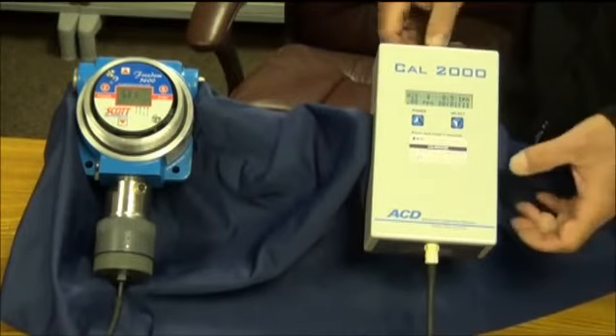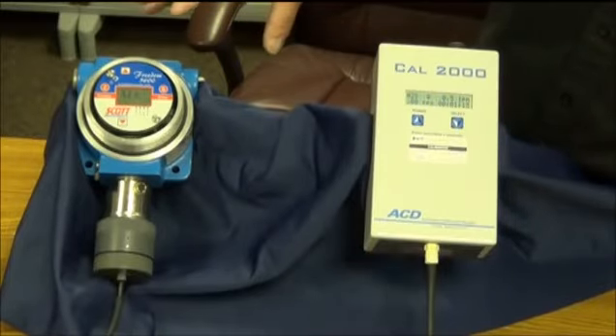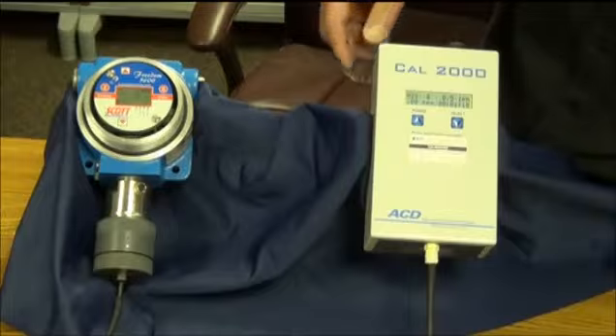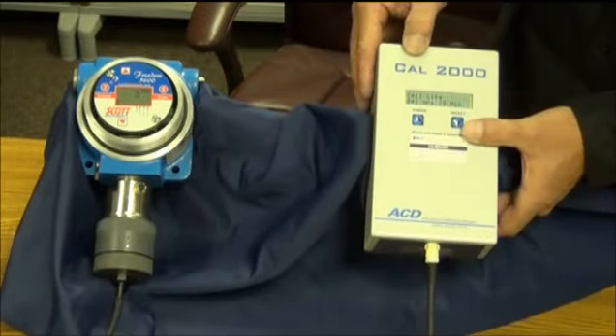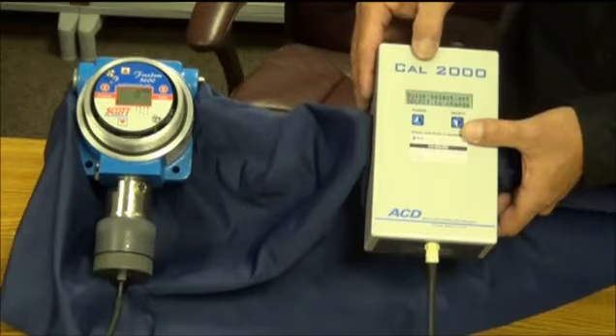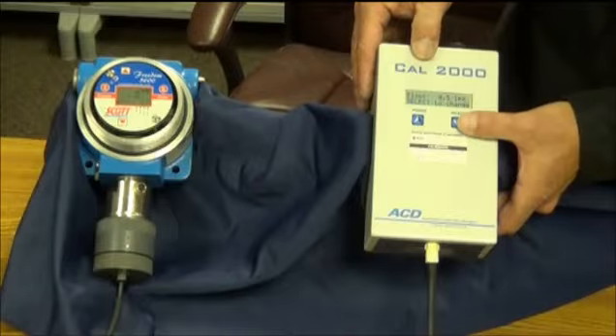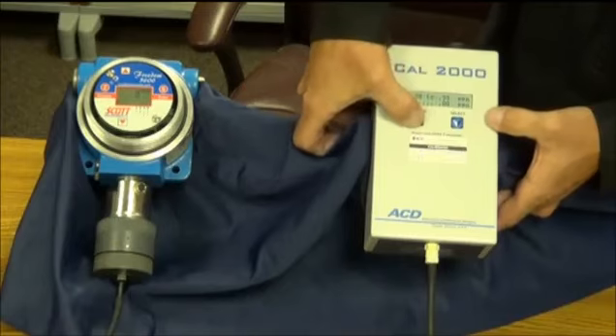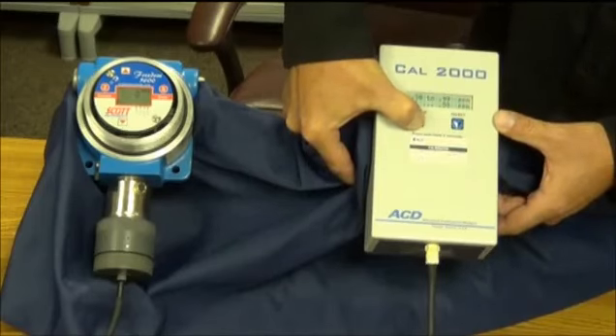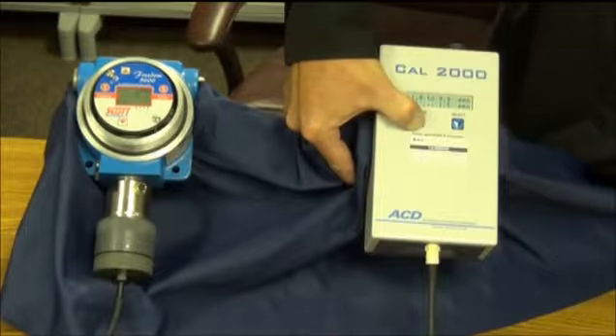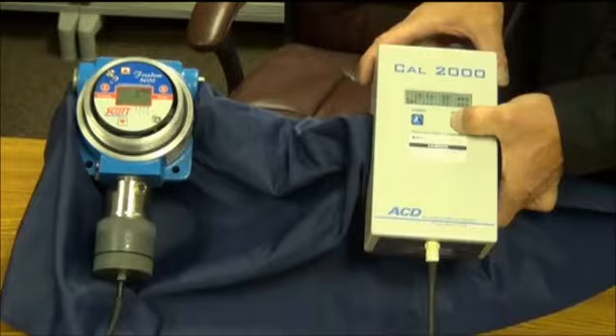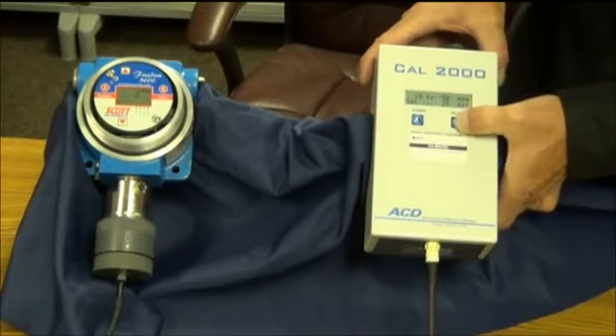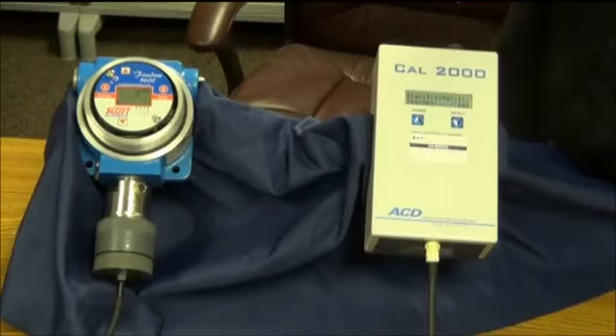Now I'm going to change the output of the Cal 2000. This is a 0 to 50 parts per million H2S sensor, so I'm going to select 25 parts per million as my calibration gas coming out of this instrument. As you saw before, it's adjustable between 0 and 50 parts per million at a half a liter a minute. So I'm going to hit select there and go up. As you can see, it's climbing. It's arbitrary where I select to calibrate this unit. Went too high. But 25 is right in the middle, so we're going to use that. Now again, once you select the output that you want, there's a 5-minute stabilization period, so we'll come back to you in 5 minutes.